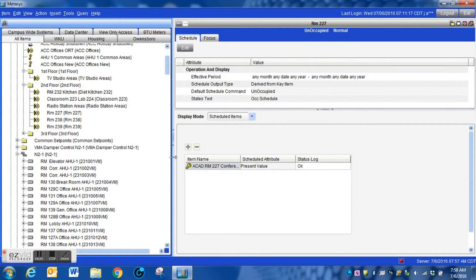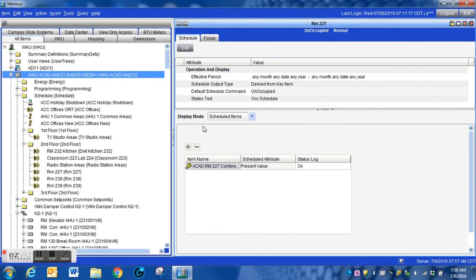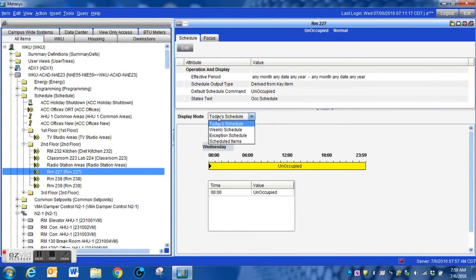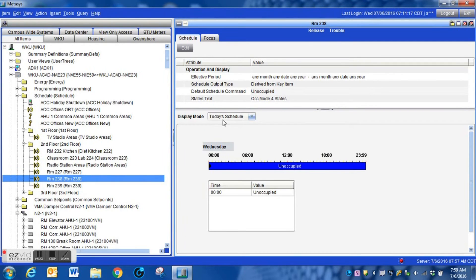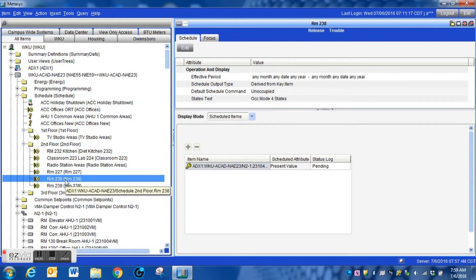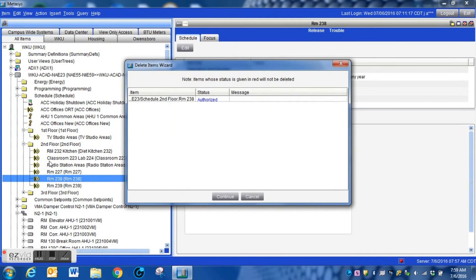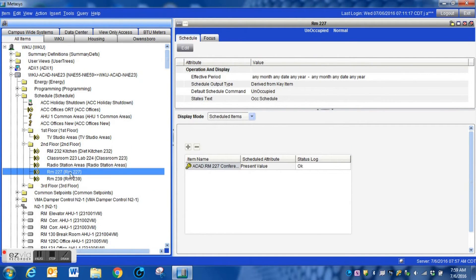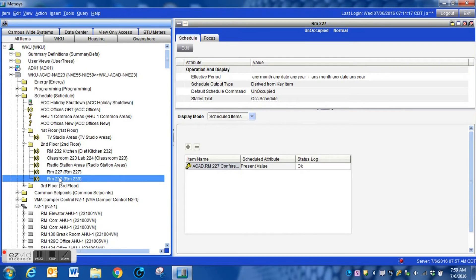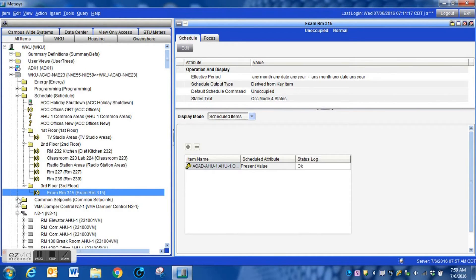Another important point about doing all of this cleanup: you need to back up your system regularly. It would not be a bad idea to have SCT open on the machine where you run your backups and actually do a couple of backups as you're going through this — that way if your system crashes you can get it back to where you were. Going through this process can upset the system enough to crash an NAE. The more unbound references you have, the more often you should do backups.